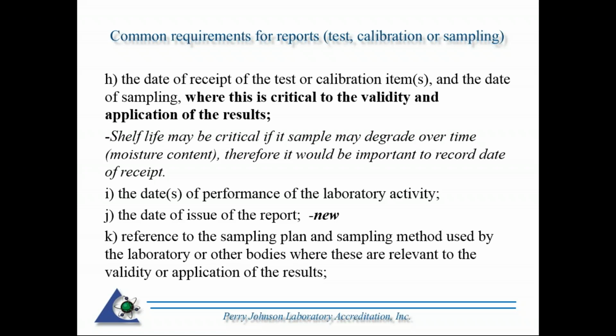The actual date of the performance of the laboratory activity, so date of test, date of calibration. Now we have a new one here, and we actually have two dates that are needed. I do realize it could be the same date, but you can see what J is, the date of issue of the report. That date of issue is the date that the report was reviewed, and whoever that individual is who is authorized to review and release reports has completed that task, then that's the date that is actually issued to the customer. So we have two dates here: the date of the performance of the activity, and the date that the report was actually issued. So the J there is new, and if shelf life was critical, it's a possibility we could have three separate dates on there.